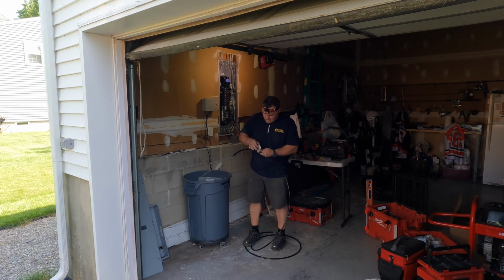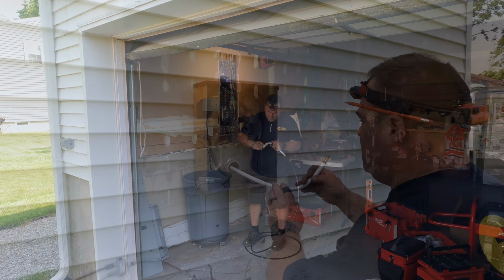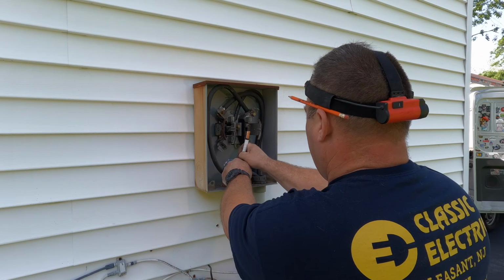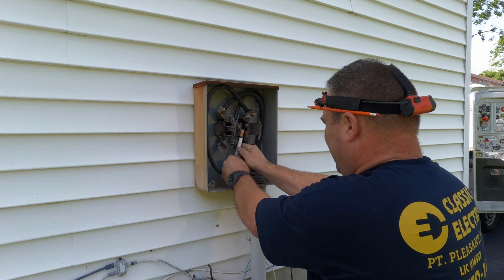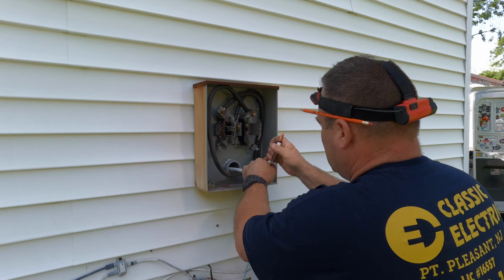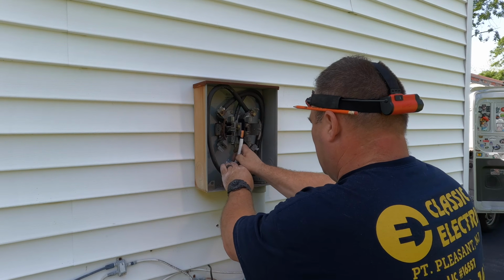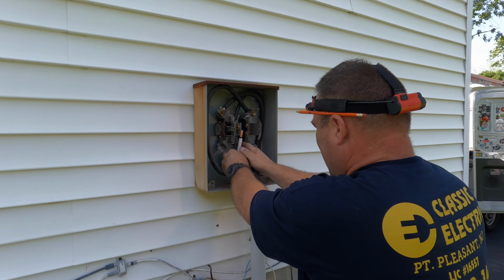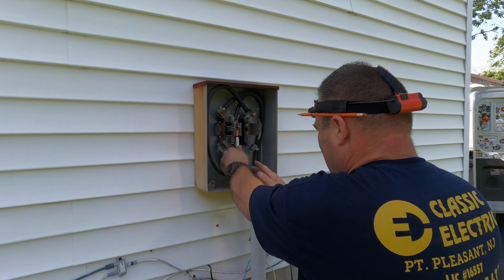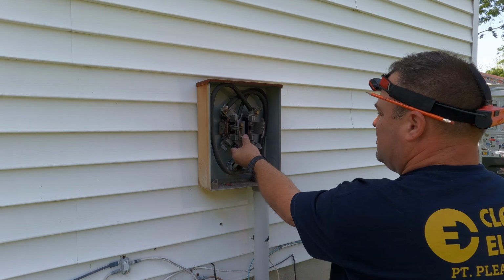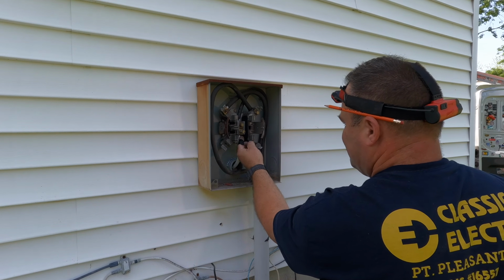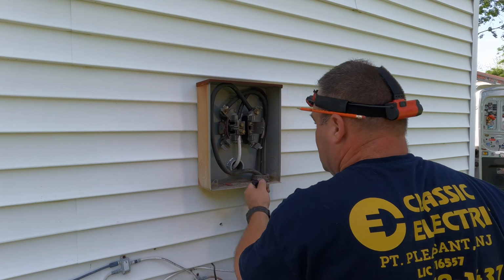So this looks like the beginning of the new service entrance conductors that I'm going to do. I'm going to do the neutral first and I like to tape it really good. That'll be the first thing that I terminate here. And see, if you don't have the wire inside the enclosure, you can make that bend with your hand rather than trying to make that bend with 4 inches of conductor right at the nipple right there. Hope that made sense.